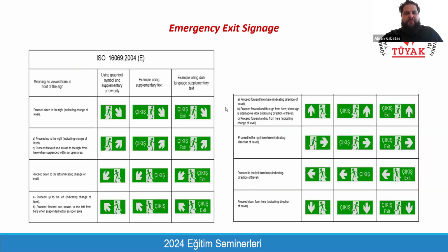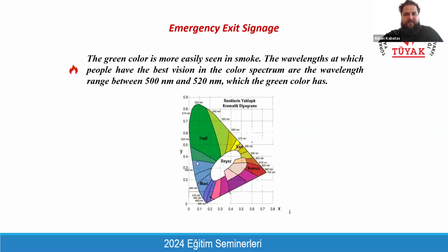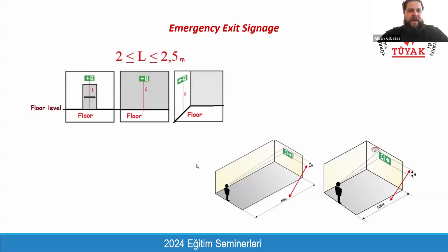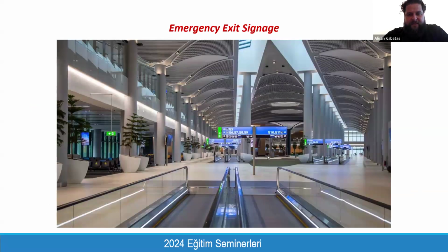These examples should be used, and we prefer to use, without letters, only this arrow and running man and door, because if you have a çıkış right on your plate, you need to provide the English translation as well for your international occupants. And the locations should be like that, so that the occupants can understand the exact location of the exit access door. This is an example from Istanbul Airport where we were the fire and life safety consultant. As you can see, these are the wayfinding plates, and we provided this special design so that it can be understood. You can understand that this is an emergency exit signage, and if you follow these green ones, you can reach the exit access. But the other ones are showing the restrooms, the restaurants, or the gates.